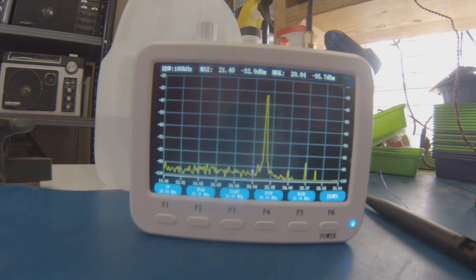Basic functions you want to do with a spectrum analyzer: it's measuring frequency versus amplitude, and that's different from an oscilloscope that does time versus amplitude.